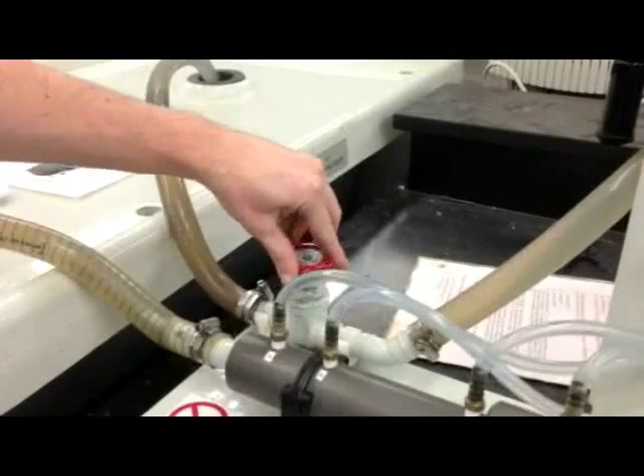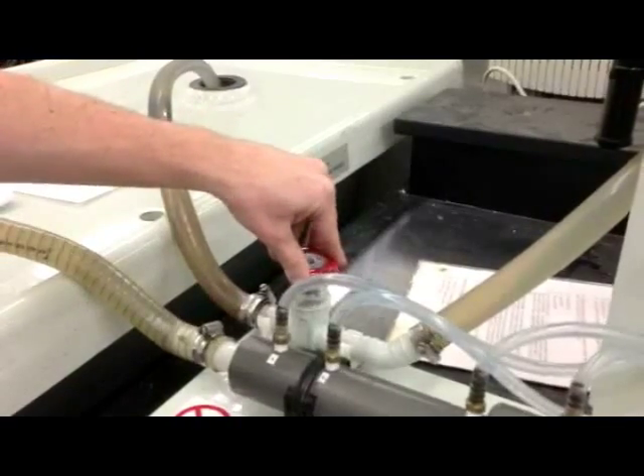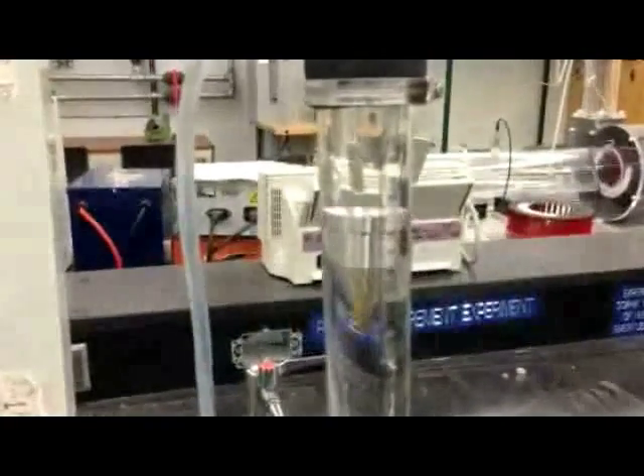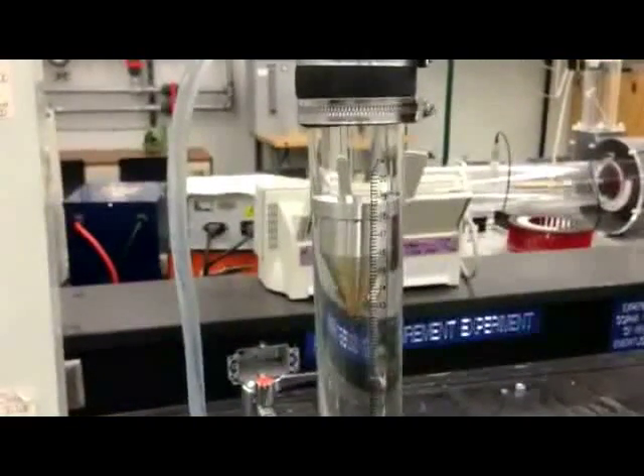Slowly open the flow control valve and continue opening the valve until either the rotameter or the water manometers reach their readable limit, whichever happens first. This will be your maximum flow rate.